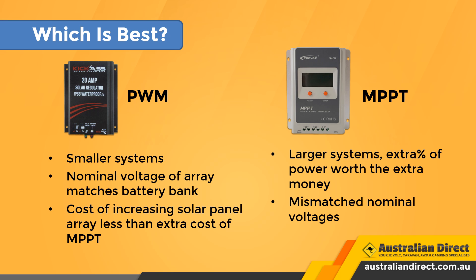An MPPT is worth it if you have a larger system that can benefit from the extra percentage of power. For instance, if you have a 2000-watt array and you can increase the output by 25% with MPPT, that's like adding another 500 watts of solar panels. At approximately $1 a watt, that's $500 just for the panels, not to mention the extra wires and racking needed — so it's probably cheaper to buy an MPPT charge controller. An MPPT charge controller is also required when the voltage of the array doesn't match the battery bank voltage. Another great reason is when the space that solar panels take up needs to be kept to a minimum but the user wants to extract the absolute maximum charge — for example, portable solar kits for camping.